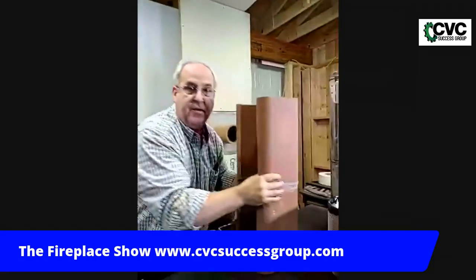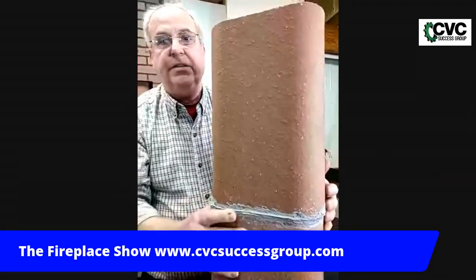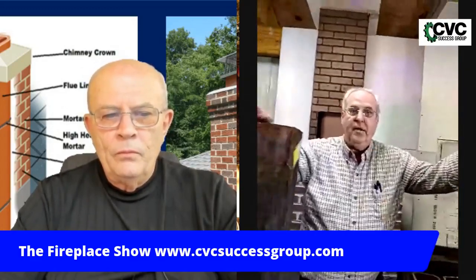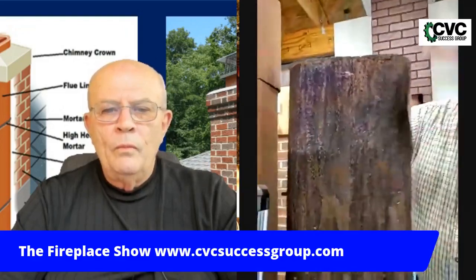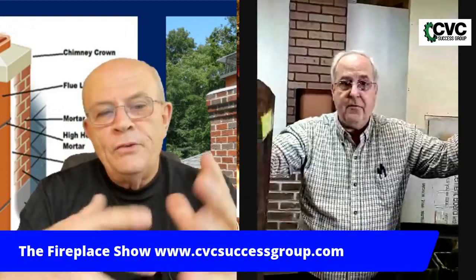This is the refractory cement that seals the outside of the liner — this is what you're supposed to have. But from wear and tear, water damage, chimney fire damage, or lightning strikes, that doesn't always happen. Clay tile is a great material to vent gases, but it's brittle. We want the American public to understand that chimneys need to be sealed, with liner sections on top of each other with a mortar joint, to prevent combustion gases from coming out on the outside of the liner.